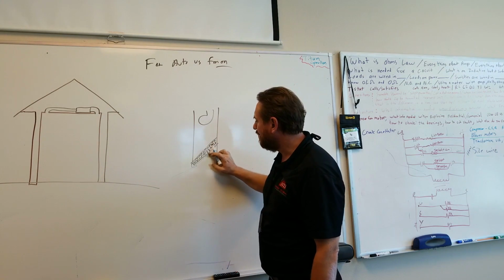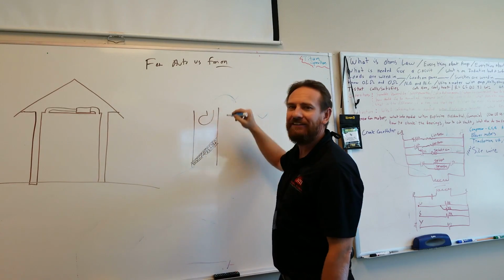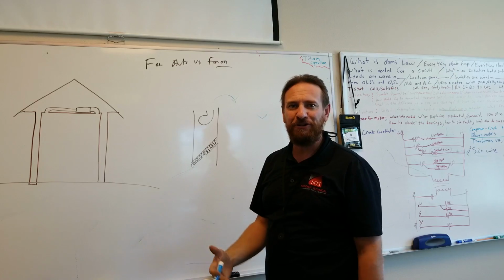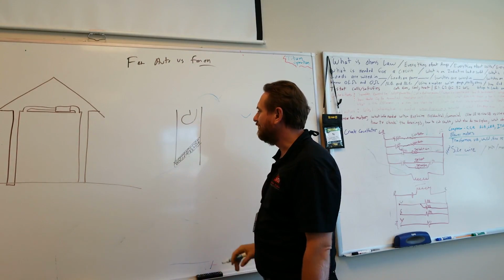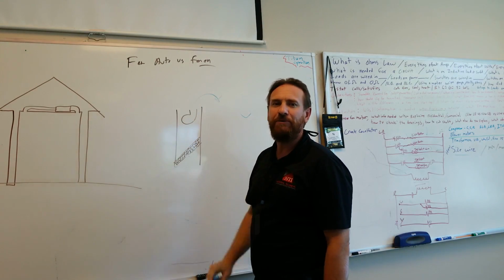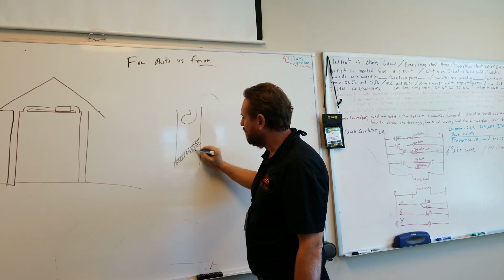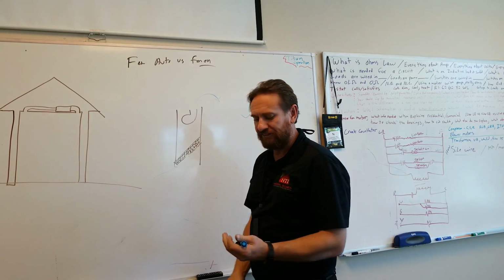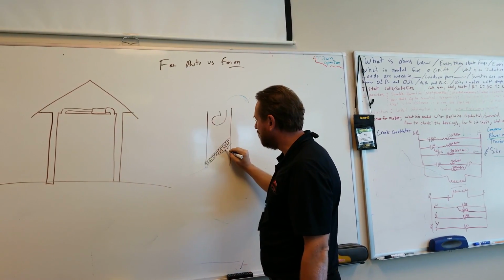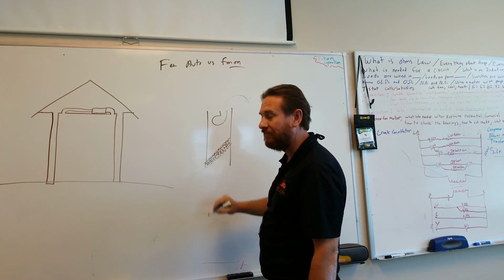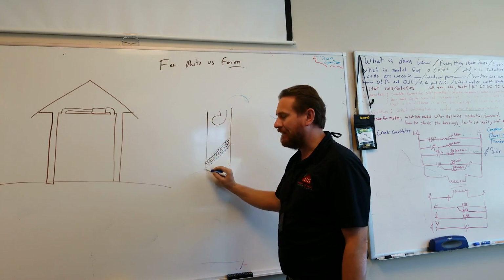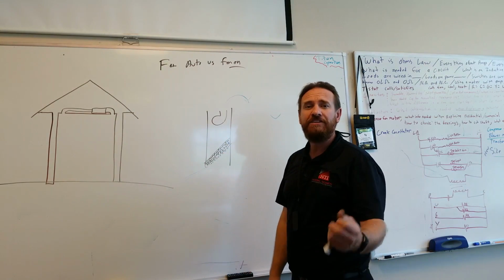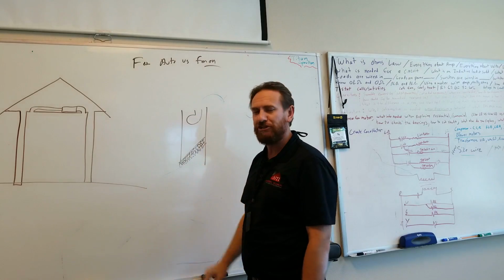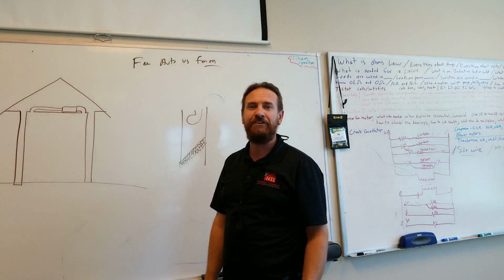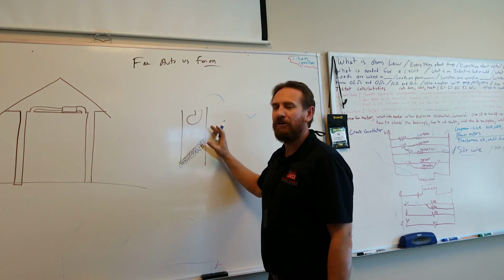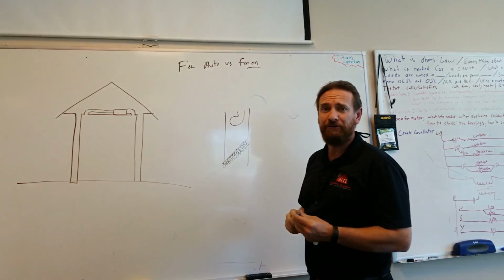And as it evaporates and goes back into the air, the coil dries out, and we're putting moisture back into the air. So as that moisture goes back into the air and becomes more humid, we lost a decent amount of efficiency. So if we have a humid climate, we for sure want this fan to cycle only when the unit's running. So now when the unit's running, we're dehumidifying, that water collects and runs outside. When the unit cycles off, the fan also shuts off, so that water that we've paid money to dehumidify, to condense out of the air, that water stays in this evaporator coil. And some of it evaporates just in this area, but it stays right there. The next cooling cycle comes on, we drop the temperature of the evaporator, we start pulling moisture out of the air, fan comes on and moves that cool air back into the house. So in a humid climate, you for sure want to have that fan run as little as possible so that we dehumidify, and also at a lower speed.